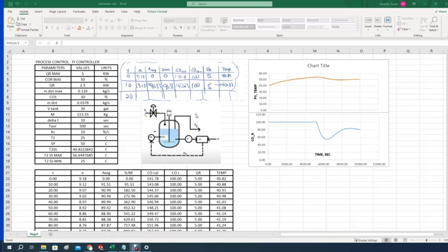Now for this system we have a resistance here. It's a heating element, and that heating element is controlled by voltage, could be a VFD, a variable voltage regulator, or a variable frequency drive, by whatever means you can control from the maximum energy that this element will emit to zero when you shut it off. Now that comes from this controller. So I measure the temperature, compare it with the set point, and then calculate the controller output that will control the flow of heat into this vessel.